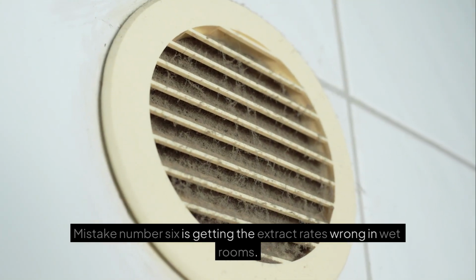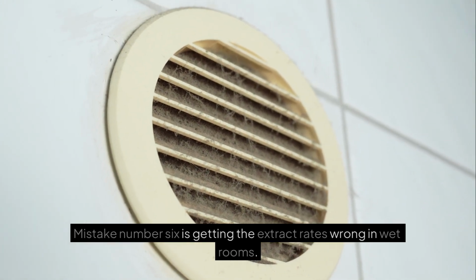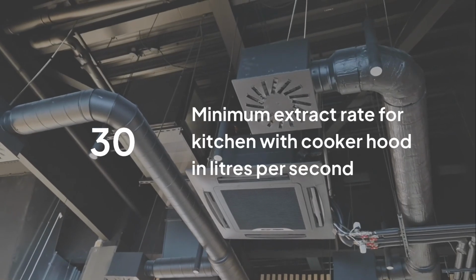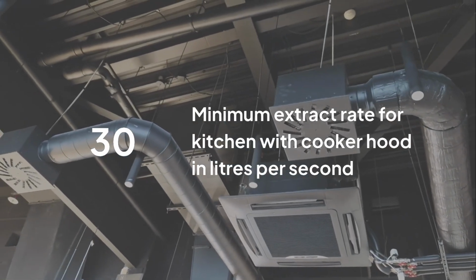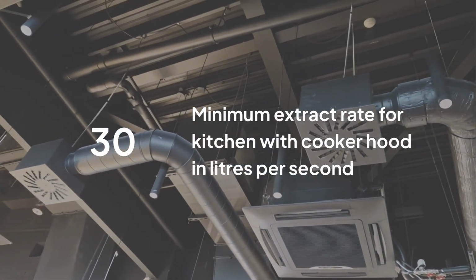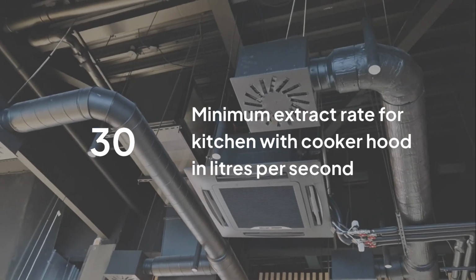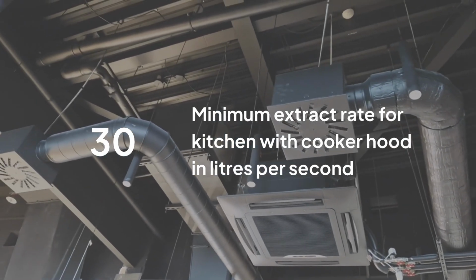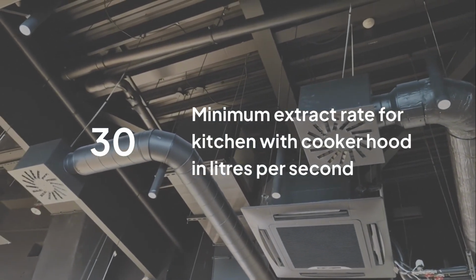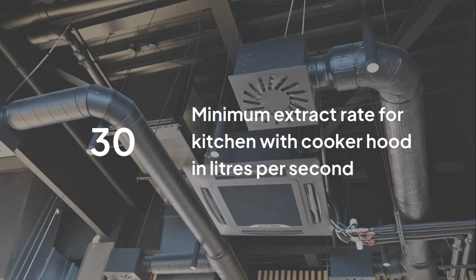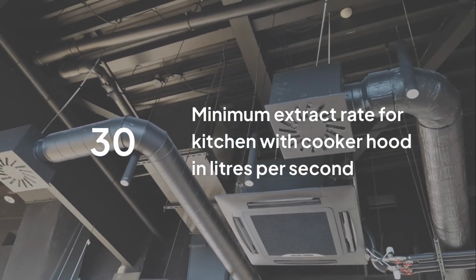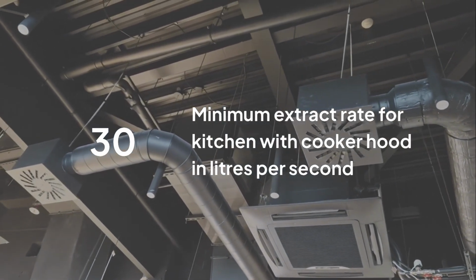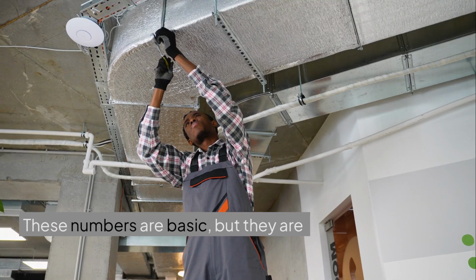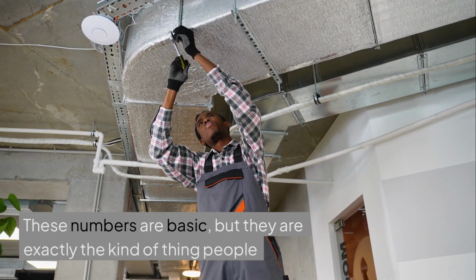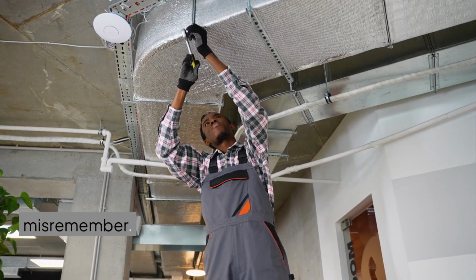Mistake number 6 is getting the extract rates wrong in wet rooms. For intermittent extract systems, Table 1.1 sets minimum rates of 30 liters per second for a kitchen with a cooker hood extracting to outside, 60 liters per second for a kitchen without one, 30 liters per second for a utility room, 15 liters per second for a bathroom, and 6 liters per second for sanitary accommodation. These numbers are basic, but they are exactly the kind of thing people misremember.